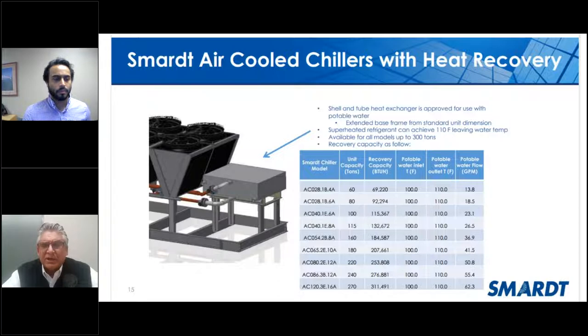The larger tonnage between 300 and 450 is not available due to the capacity needed for the condenser itself, right? But it has a shell and tube heat exchanger, and it's not your standard brazed plate that most manufacturers use for a desuperheater in those applications.